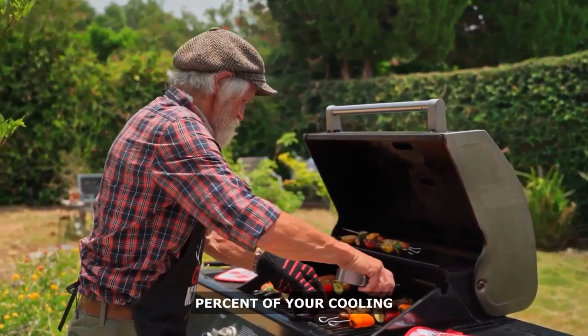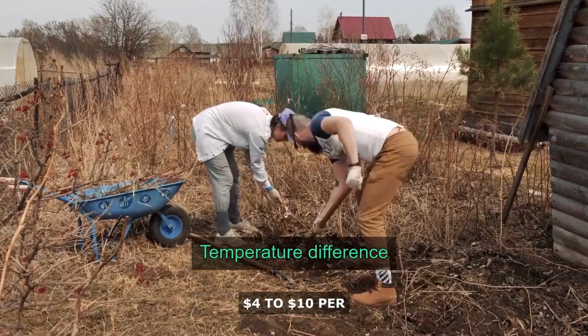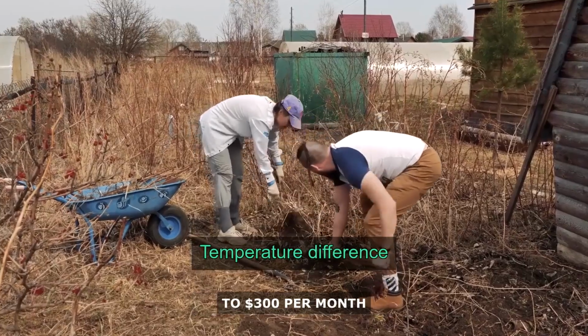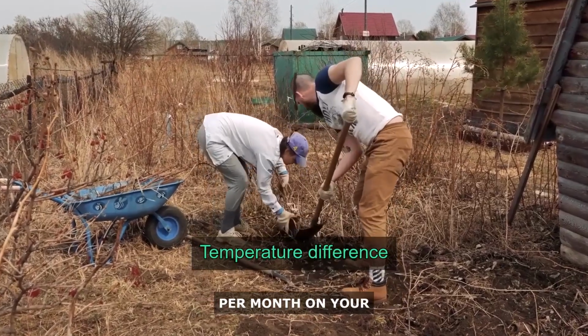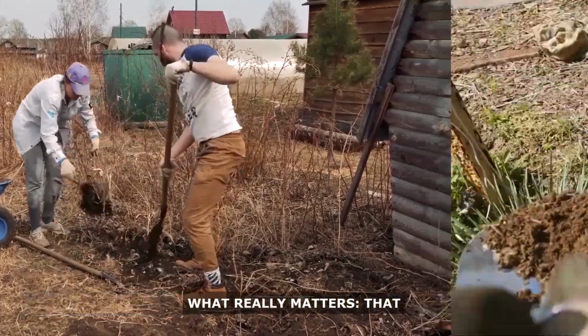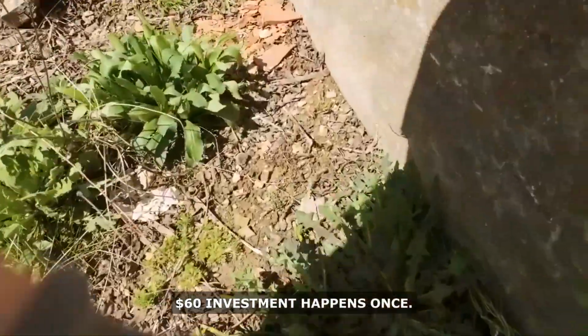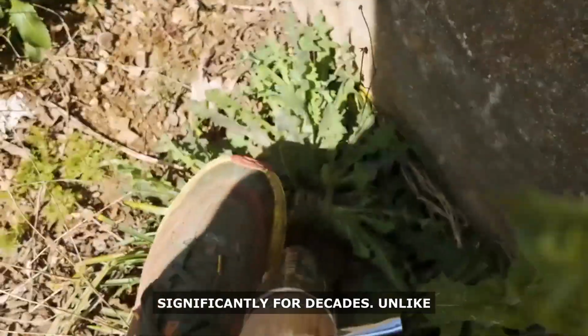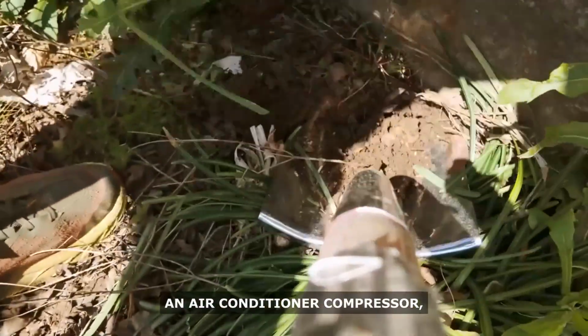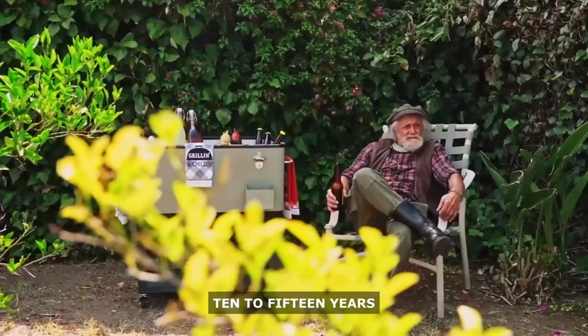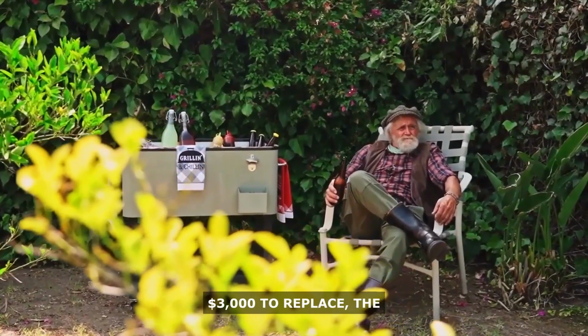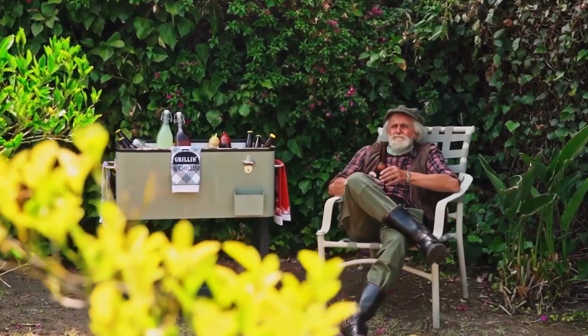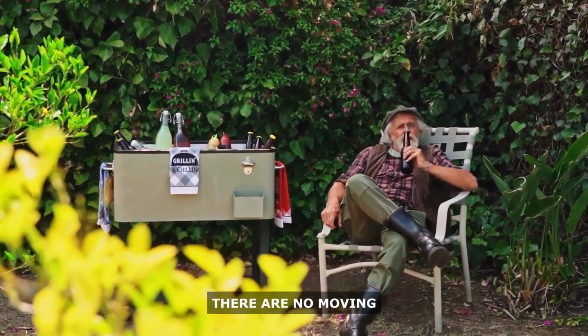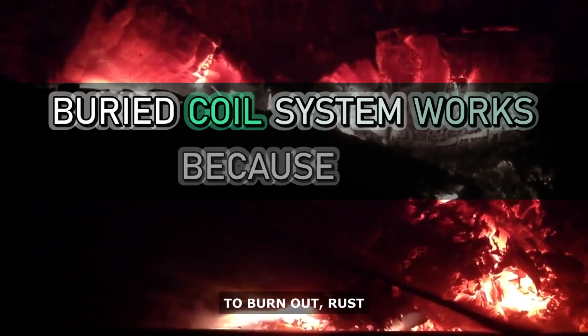But here's what really matters. That $60 investment happens once. The materials don't degrade significantly for decades. Unlike an air conditioner compressor, which can fail after 10 to 15 years and cost $1,500 to $3,000 to replace, the buried coil system is just tubing and water. There are no moving parts underground. There's nothing to burn out, rust through, or require a service call. You maintain the surface equipment, the pump and fan unit. On a fixed income, that changes everything.